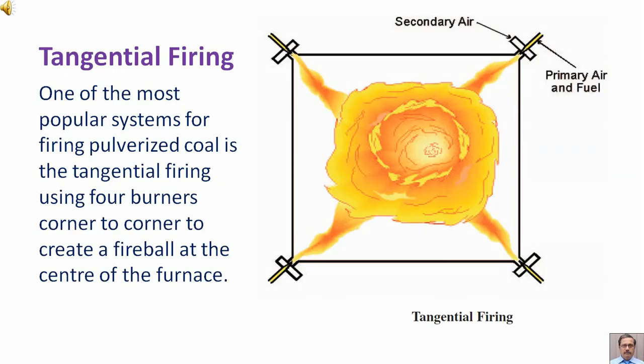Before discussing burner tilt, we have to discuss tangential firing. One of the most popular systems for firing pulverized coal is tangential firing, using four burners corner to corner to create a fireball at the center of the furnace. Here in the diagram, we can see the fireball.